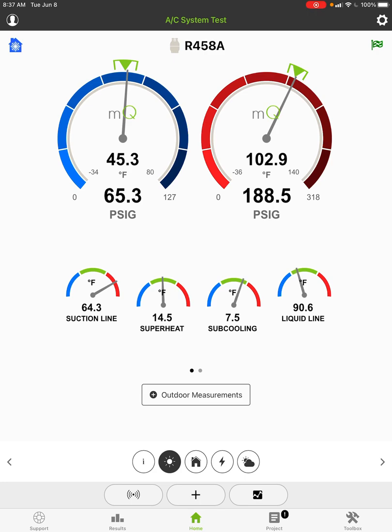So they are different, but this is the correct way of doing it. Hopefully some of the other manufacturers will pick up on this and do the same at some point. The only reason we measure pressure is to get the corresponding saturation temperature or to get the temperature of the coil. You'll see this most pronounced on refrigerants like R458A or Bluon, which is a high-glide refrigerant, and not so much — but still a little — on refrigerants like 410A. On a pure refrigerant like R22, they'll agree.